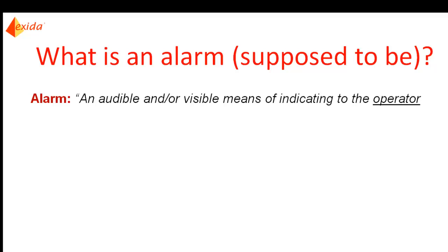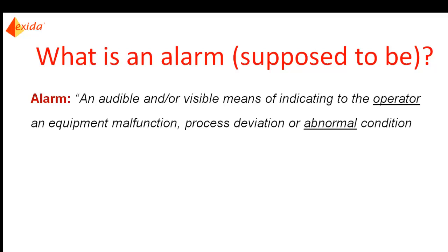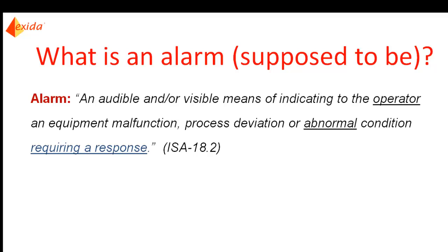Therefore, all of the information in the alarm system must be easily understood, useful, and actionable to the operator. An alarm should also indicate an equipment malfunction, process deviation, or abnormal condition, which means that something is wrong. Alarms should not be used for expected conditions or events. And last but not least, an alarm requires a response.